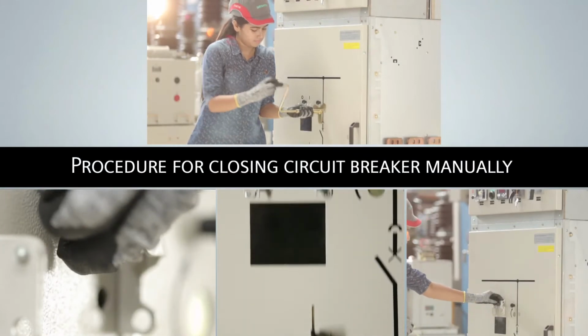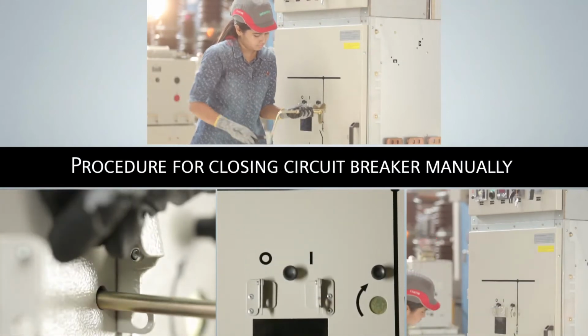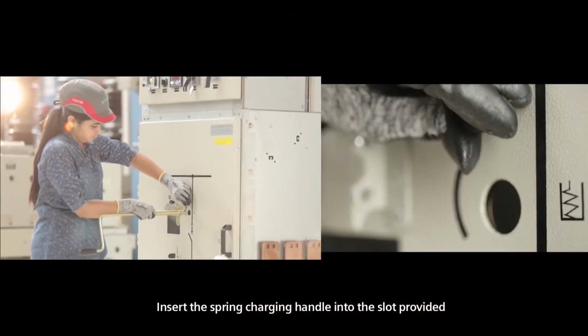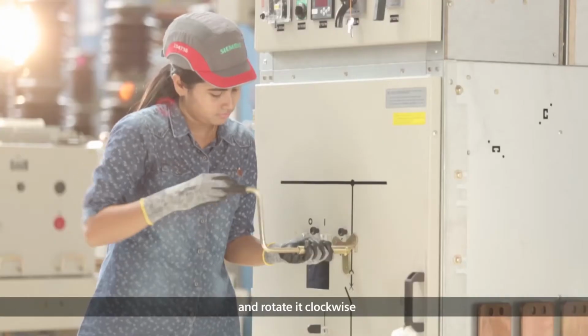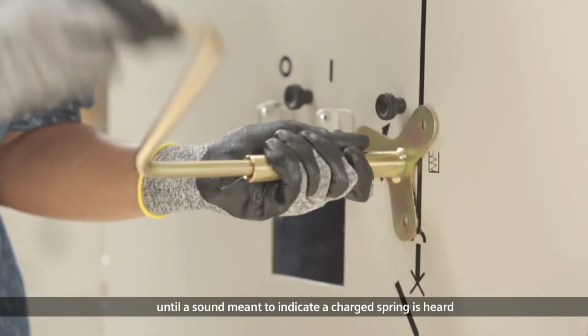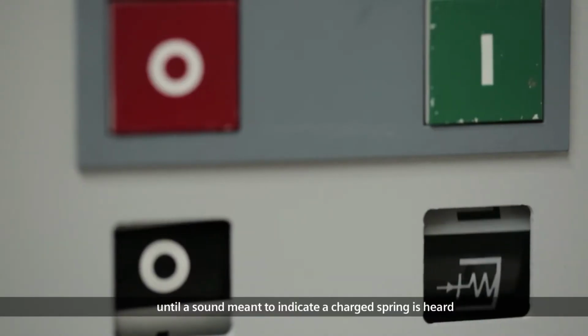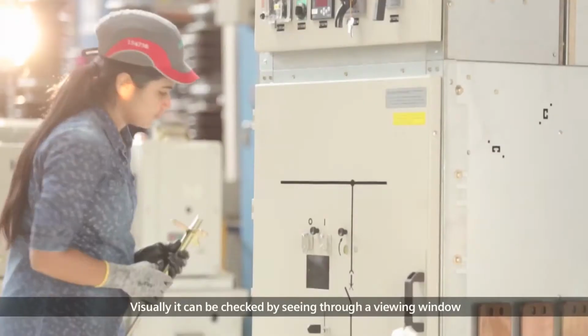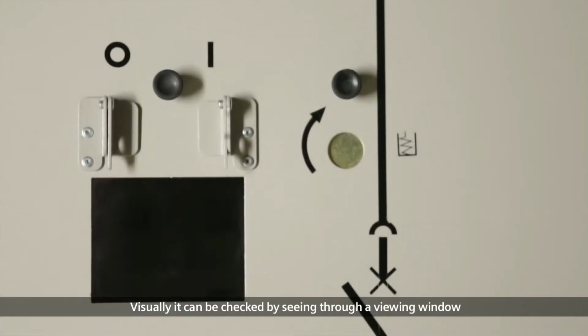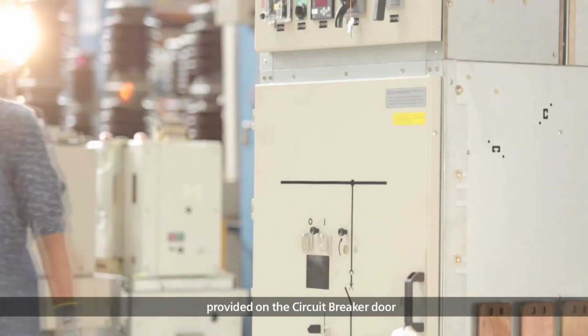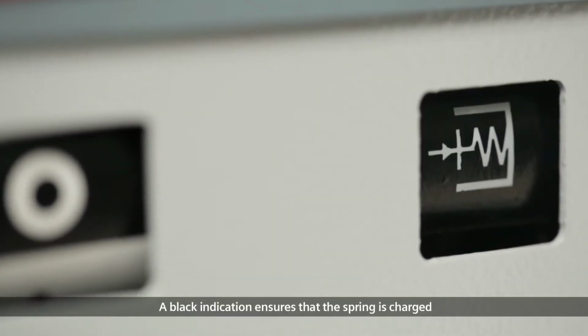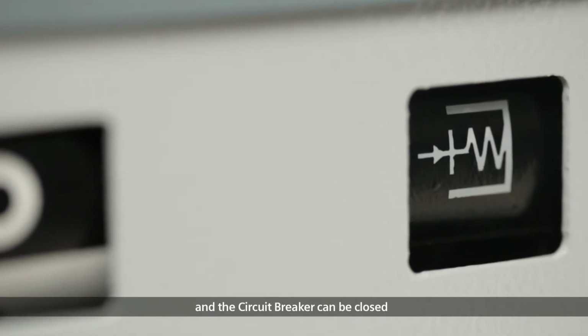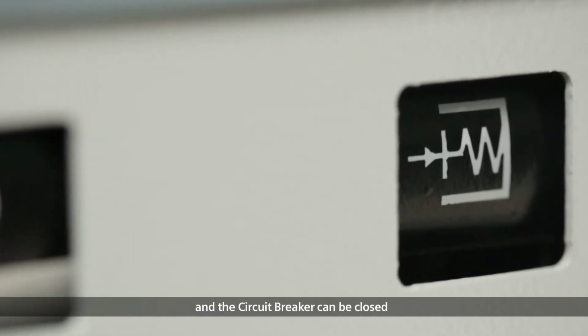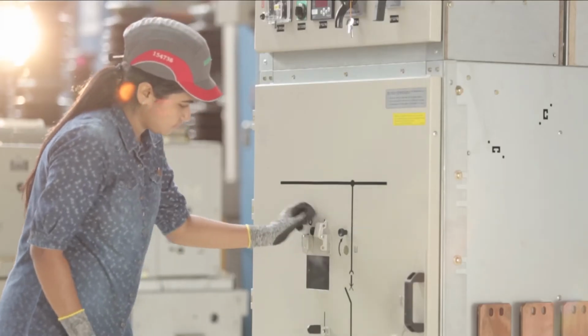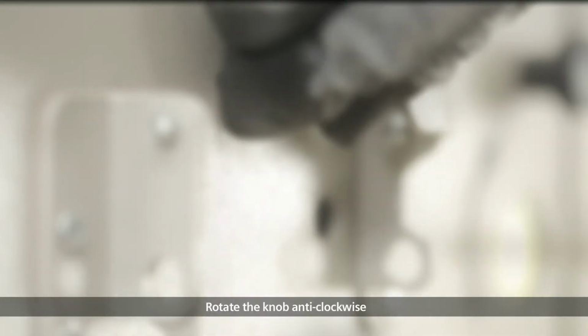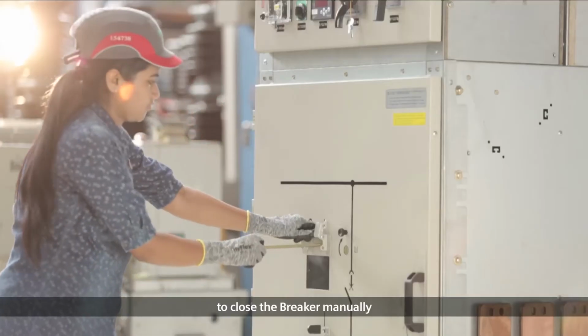Procedure for closing circuit breaker manually. Insert the spring charging handle into the slot provided and rotate it clockwise until a sound meant to indicate a charged spring is heard. Visually, it can be checked by seeing through a viewing window provided on the circuit breaker door. A black indication ensures that the spring is charged and the circuit breaker can be closed. Rotate the knob anti-clockwise and insert push rod to close the breaker manually.